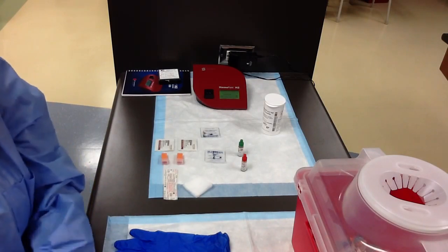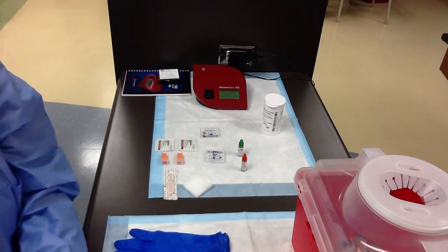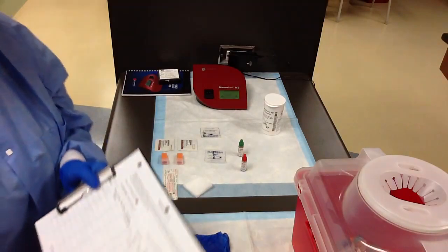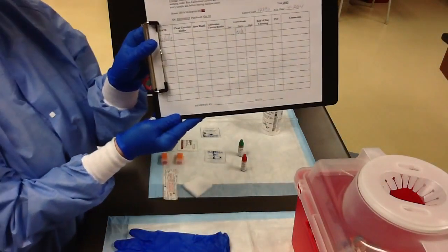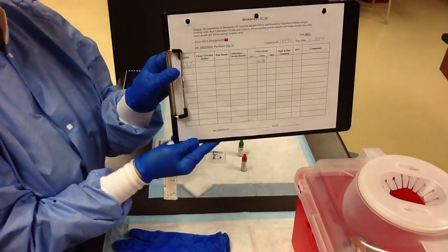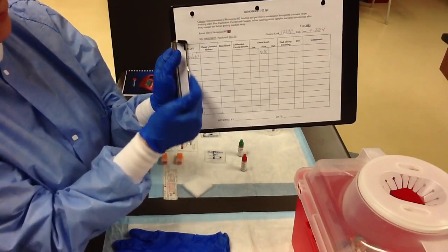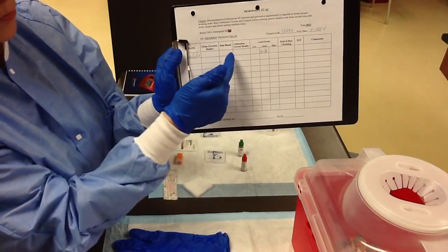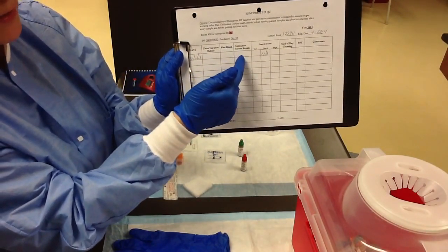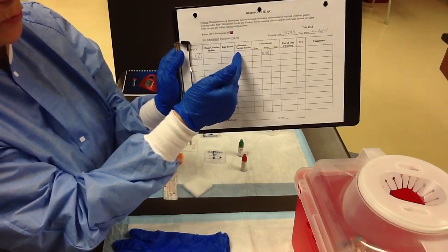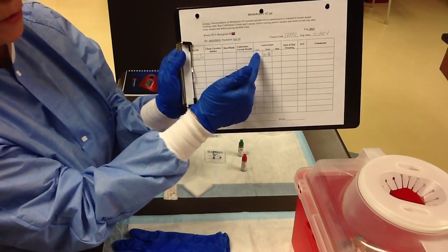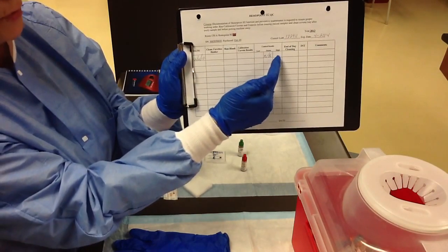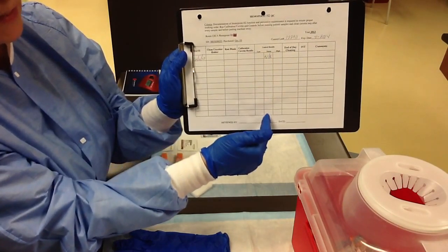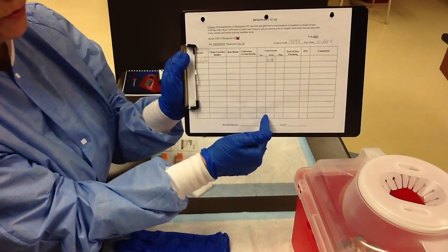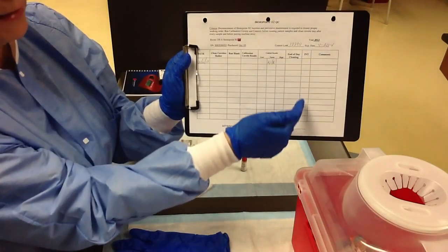While that machine is running, I'm going to show you a typical log sheet. On this side, we're going to have the date. We're going to have the calibration results, which I'm going to record here, the results of the low control, the high control. We are not running a normal control today. It's not necessary to run more than 2 controls. And I'll put my initials.